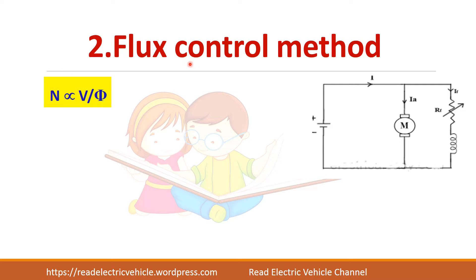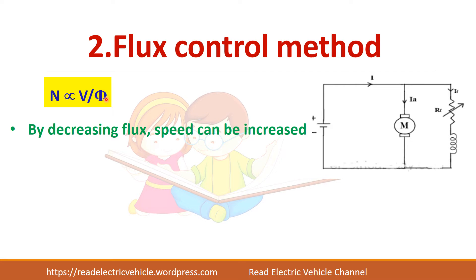Next you have the flux control method. Again the same formula: N is directly proportional to V by phi, but here we are changing the flux. So how to change this flux? You put a resistor in series with the field winding, so the field current will change, which means the flux can be changed. As flux decreases, speed will increase.